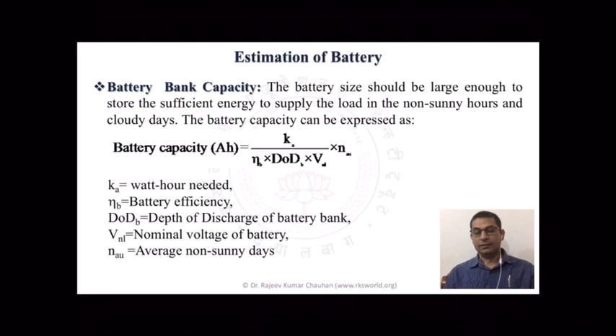But no manufacturer claims that the battery can be used from 0 to 100%. Every manufacturer gives some fixed value of the state of charge, it could be like 20 or 30%. If we discharge the battery below the given state of charge, that may damage or degrade the battery and affect the battery life. For example, if a battery has a warranty of 3 years, and we discharge the battery below the specified SOC level, that battery may get damaged before its warranty period.